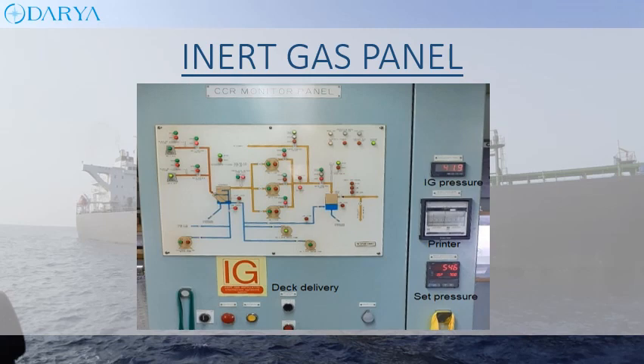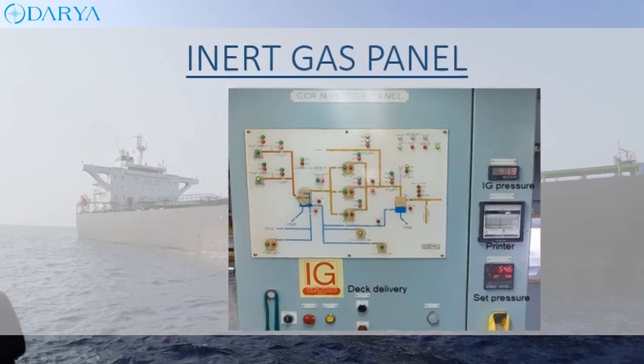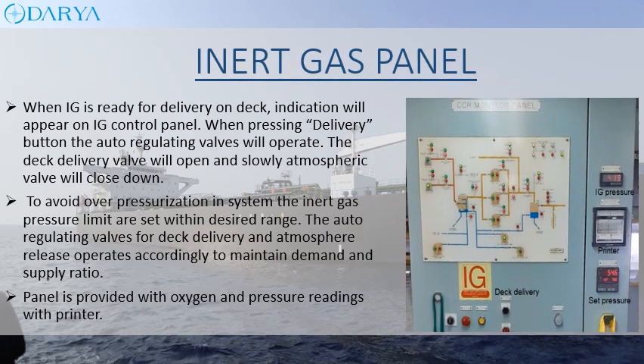When IG is ready for delivery on deck, an indication will appear on the IG control panel. When pressing the delivery button, the auto-regulating valves will operate: the deck delivery valve will open and slowly the atmospheric valve will close down. To avoid over-pressurization, the inert gas pressure limits are set within a desired range. The auto-regulating valves for deck delivery and atmosphere release operate according to the maintained demand-to-supply ratio. The panel is provided with oxygen and pressure readings with a printer.